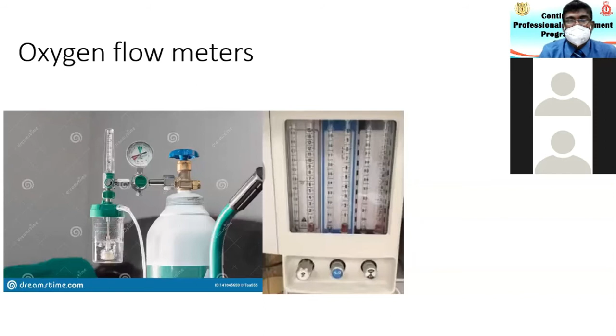Why do we call it an oxygen regulator? Because these cylinder gases are regulated as they come out. These cylinders containing oxygen, what is the full capacity, how much pressure is inside a fully filled cylinder? It is about 137 bar, so 137 times the atmospheric pressure. You can see that from this pressure gauge, and then it comes to this flow meter, usually calibrated to about 15 liters. You can give about 15 liters, and then this oxygen goes through this humidity water bath.